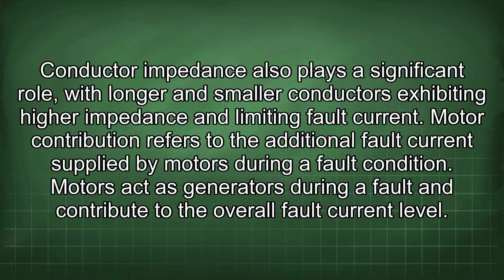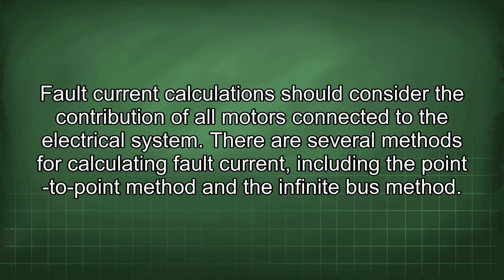Conductor impedance also plays a significant role, with longer and smaller conductors exhibiting higher impedance and limiting fault current. Motor contribution refers to the additional fault current supplied by motors during a fault condition. Motors act as generators during a fault and contribute to the overall fault current level. Fault current calculation should consider the contribution of all motors connected to the electrical system.